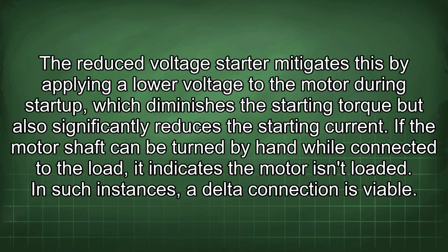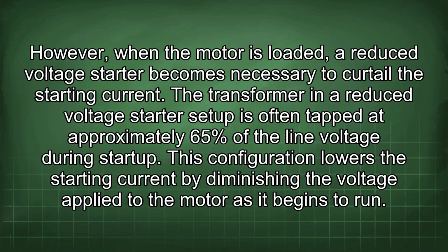If the motor shaft can be turned by hand while connected to the load, it indicates the motor isn't loaded. In such instances, a delta connection is viable. However, when the motor is loaded, a reduced voltage starter becomes necessary to curtail the starting current. The transformer in a reduced voltage starter setup is often tapped at approximately 65% of the line voltage during startup.